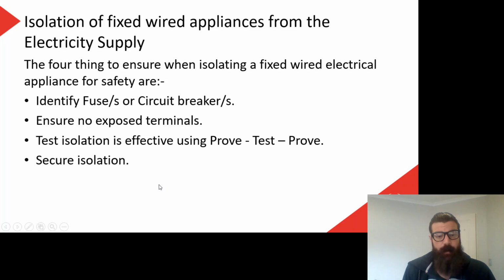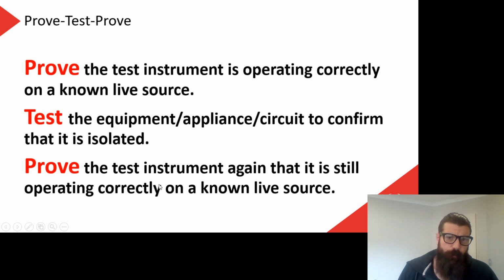So securing that. And here is our prove, test, prove. So we prove the test instrument is operating correctly on a known live source. So this is normally when we're testing for voltage, we're doing prove, test, prove. I'm going to go to a socket or some power source that I know is live. I could do it on the mains entry into the switchboard, whatever, but something I know is live, and I test that, and I should get 230 volts or 400 volts or whatever the voltage is there. That proves that my meter is working.